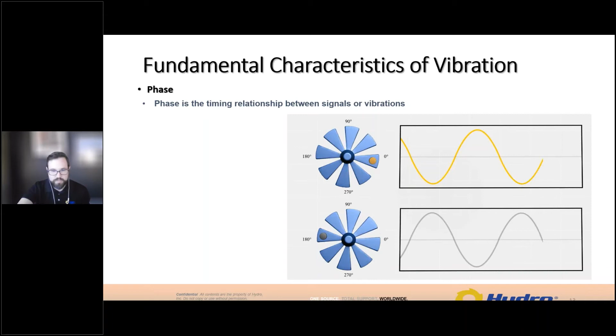Sinusoidal patterns aren't really what you're going to see in terms of vibration—you'll see much more complicated time waveforms when capturing that vibration over time. The way we analyze those is by breaking complex time waveforms down using the fast Fourier transform method. This takes the complex time waveform and splits it out into individual frequencies, each with their own amplitude and frequency. Once each is split out individually, you recombine them in a different way to show a spectrum, displaying frequency and amplitude instead of time and amplitude.